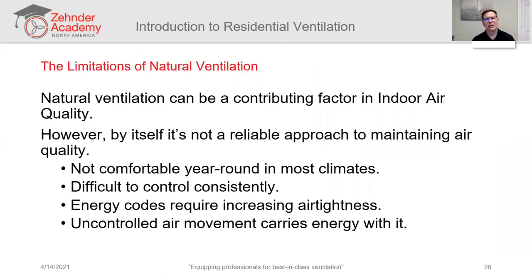So there are limitations on natural ventilation. It can be a contributing factor in indoor air quality, but it's just typically not a reliable approach. It's not comfortable year round in most climates. It's difficult to control consistently. You've got to rely on the wind or your heating system or something. Energy codes are trending in the opposite direction, requiring increasing air tightness. And of course, uncontrolled air movement in and out of the building carries energy with it. And so that's not necessarily helpful.